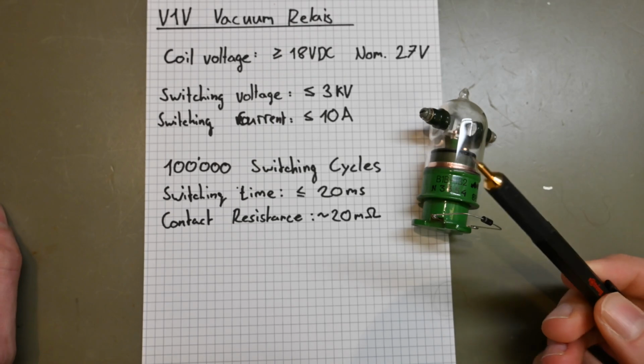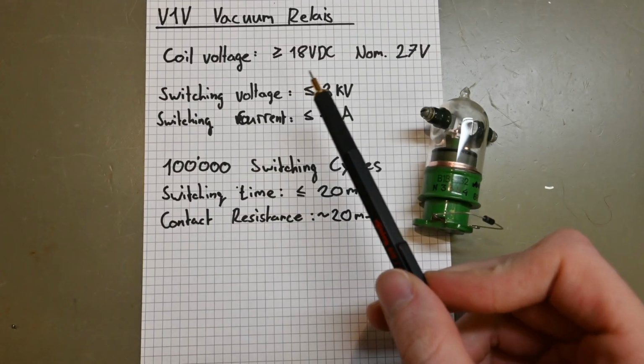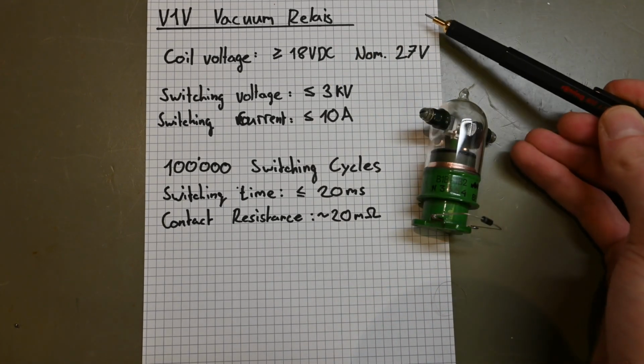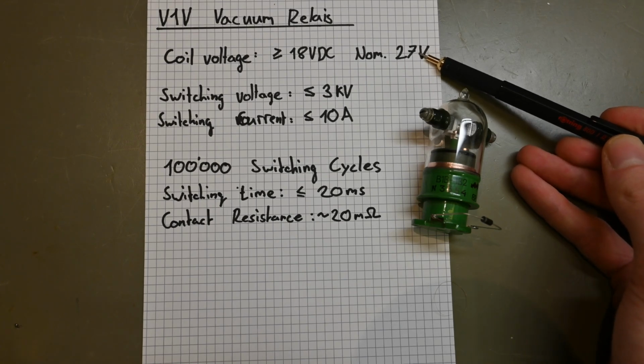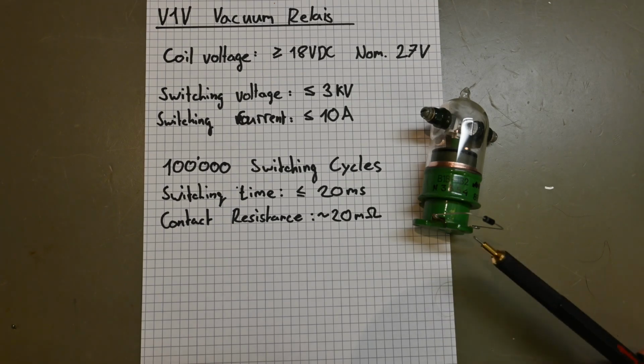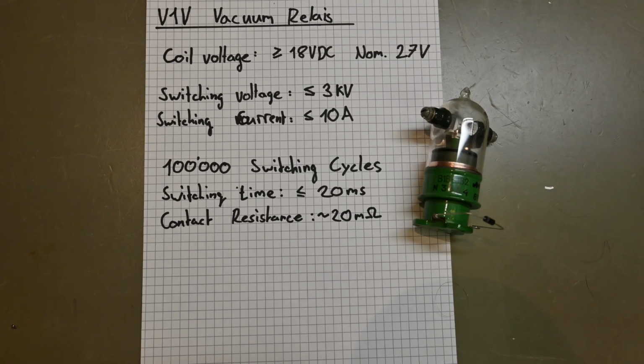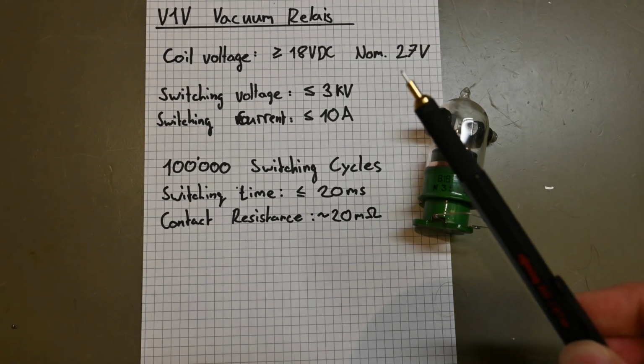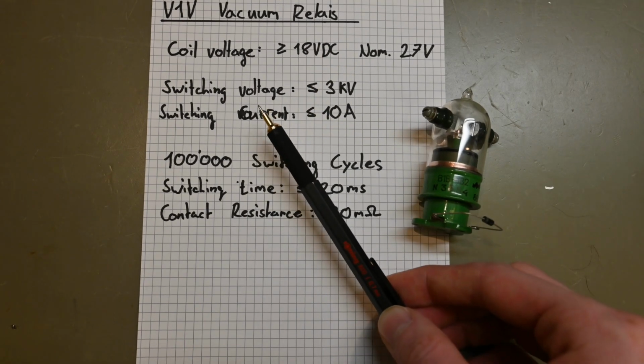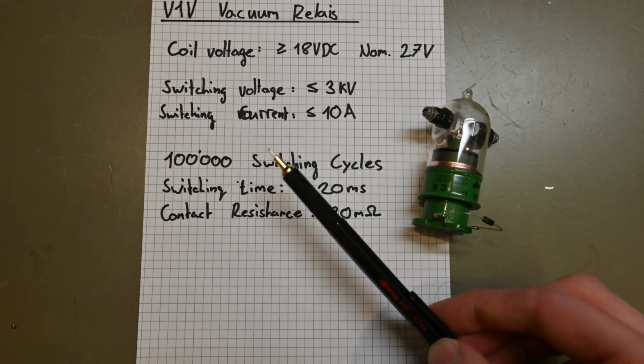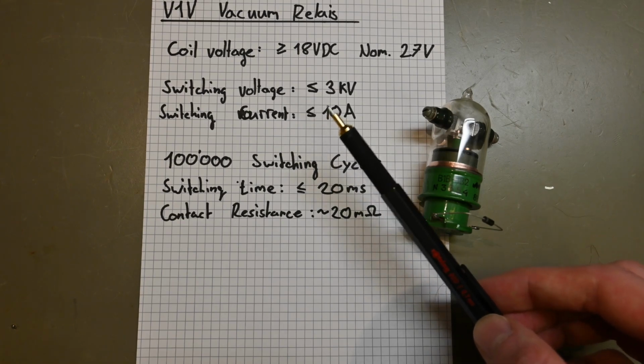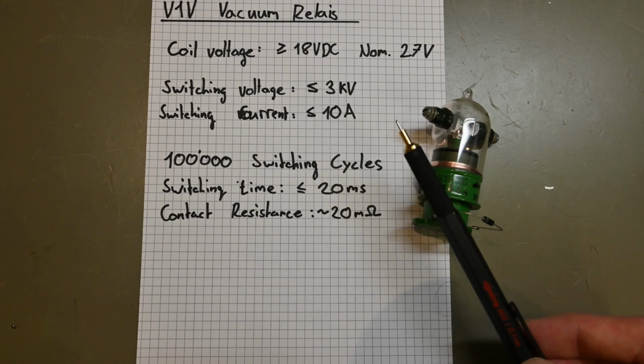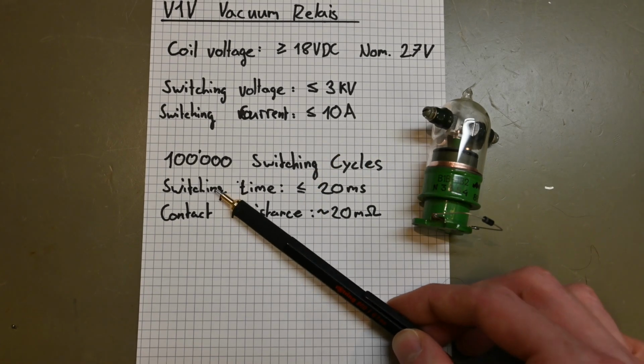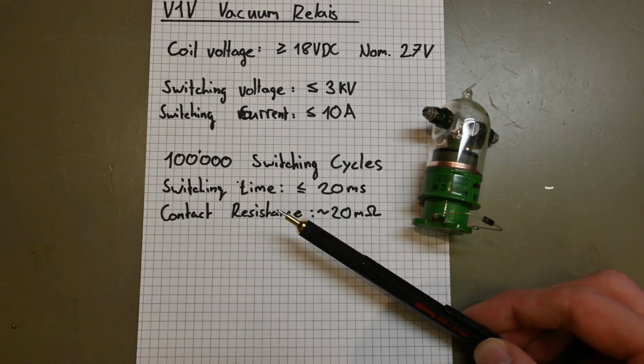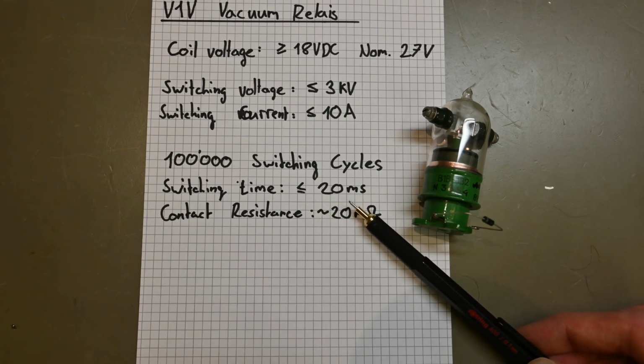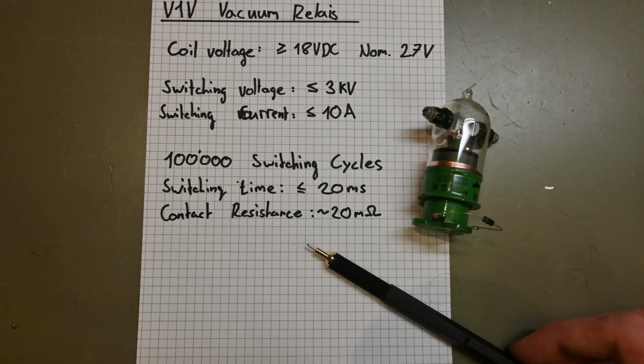So, as I said, this is a vacuum relay. It has a coil voltage of about 18 volts DC. In the datasheet they say a nominal voltage of 27 volts is applied to the coil, but it will switch at a voltage greater than 18 volts. About the switching characteristics, we have a switching voltage of 3 kilovolts and a switching current which has to be smaller than 10 amps. They say it can last about 100,000 switching cycles, and the switching time is smaller than 20 milliseconds. The contact resistance is about 20 milliohms.